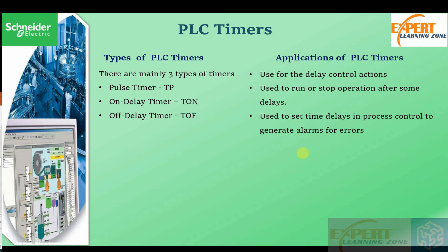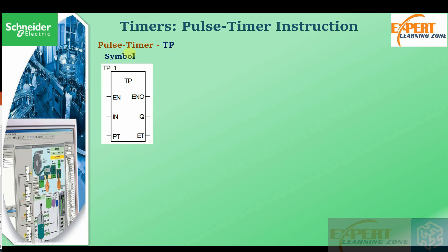We will start with the first type of timer, the pulse timer called TP. This is the symbol for the pulse timer. Like mentioned in an earlier tutorial, every function block has the enable and error notification parameters. Pulse timers also have different parameters: the input parameter used to start the timer, the preset time which determines how long the timer will run, the elapsed or internal time which progressively counts the timer, and the output which indicates whether the preset time has been reached.